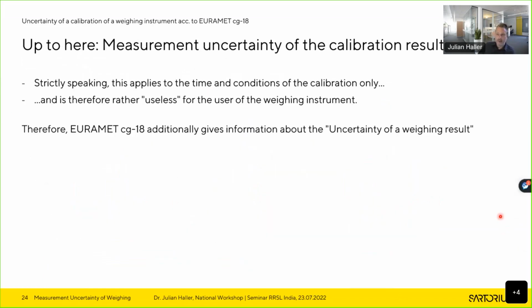Now, up to here, I just talked about the measurement uncertainty of the calibration result. And the bad news is that, strictly speaking, this applies, of course, only to the time and conditions of the calibration and is also only given at some discrete points. You usually will have a calibration at 5 or 10 test loads. So you only have the information about the calibration uncertainty at these 5 or 10 test points. So for the user, this is rather useless information. That might be a bit hard, but actually the user may not use this calibration uncertainty as the uncertainty of his weighing process. And therefore, actually, the Euramet CG18, fortunately, gives additional information about how the uncertainty of a weighing result in use can be determined.